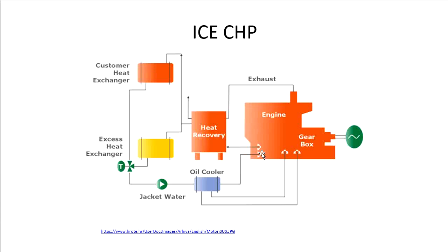Now some typical values of the heat and power regarding how fuel gets converted by the internal combustion engine. So in rough calculations, with power outputs of, let's say, dozens of kilowatts, the efficiency of electricity production can be around 1/3, let's say 30–33%.